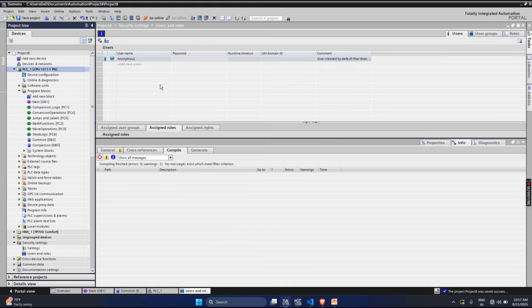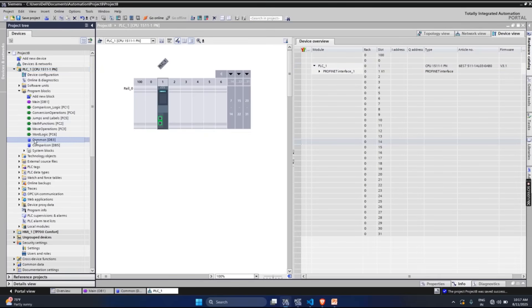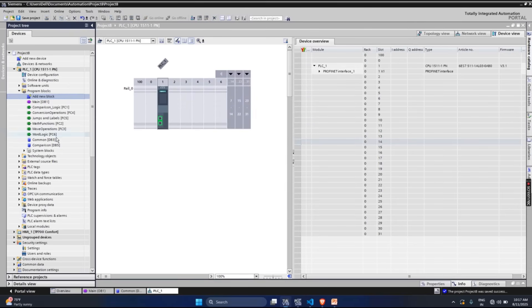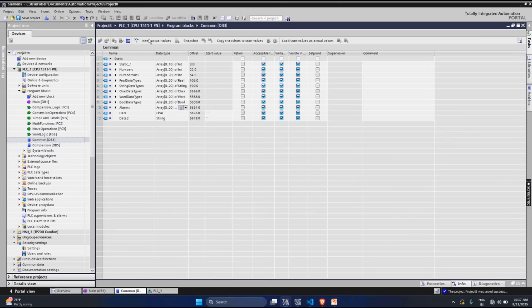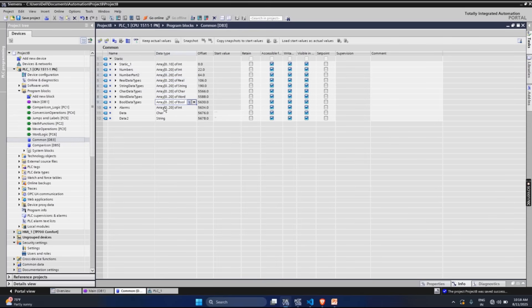Once compilation is done, we will be downloading our project to the PLC. But before that, we need to create a DB. You can create a DB by double clicking on 'Add a new block', selecting 'Data block', global DB, name it whatever you want, and go to manual to change the DB number. I have already created it. Open that DB and create variables — a list of different data types which we need to read and write in the PLC. Here you can see I have created integer, real, string, character, word, and boolean data types.